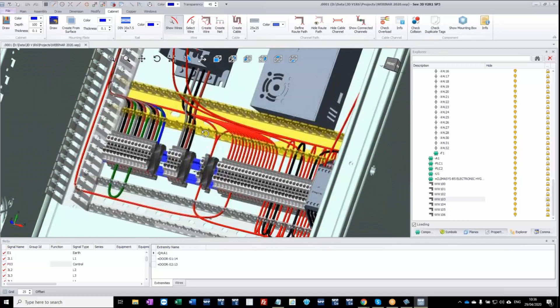If I drag this bar across, I can see at this particular point, the orange area at the top is the 20% spare that I want to define and keep. If I had too many cables, this green box would be right up to the top and would turn red to indicate a problem, that the cableway is too small. In this situation, there's no problem, there's plenty of space. But if there was a problem, we could change it to a larger cableway or move some components elsewhere.